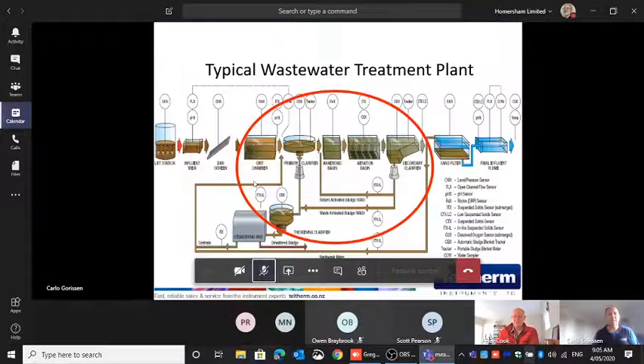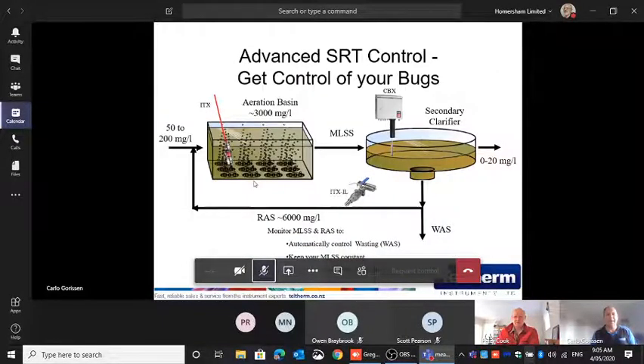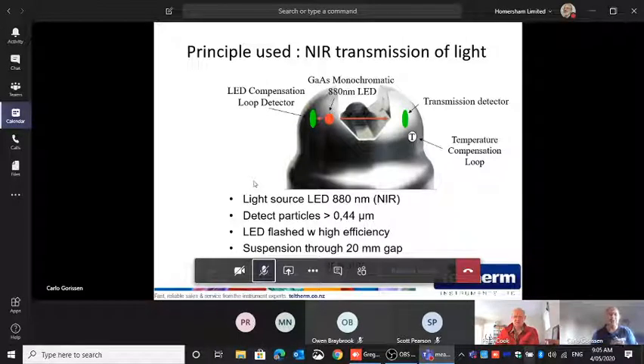What you'll see, for instance, is what a wastewater treatment plant is. I think we all know that. It doesn't matter which plant it is, or for Cerlic. The most important thing is how it works. The unit uses an LED with an 880 nanometer wavelength. That means we can see particles bigger than 0.4 microns. That is the same as the filter you use in your dry weight sample, which is basically a 0.4 micron filter. So we can tell people that our accuracy is the same as your lab sample.